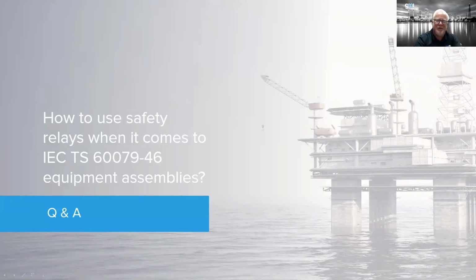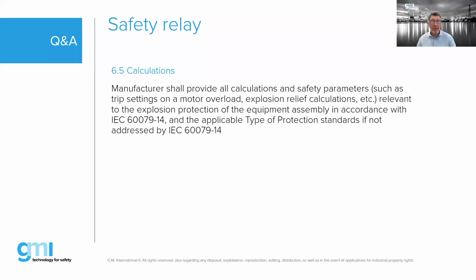Okay. So this was a question we got during the registration phase. Bob, the question: how to use safety relays when it comes to IEC TS 60079-46 equipment assemblies. I'll let you, Bob, run through it. Right. So the IEC 60079 TS, and an IEC TS is different from an IEC standard. A TS is a technical specification, and in many cases it's a precursor to an actual IEC standard. This was published not too terribly long ago, talking about equipment assemblies.